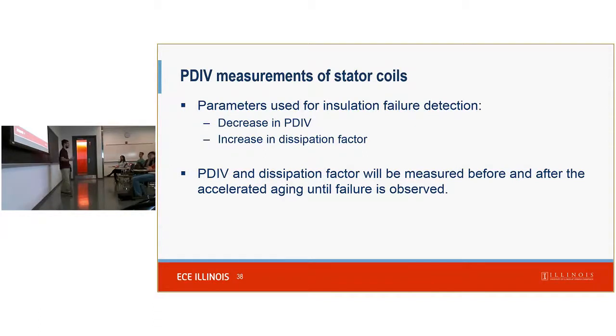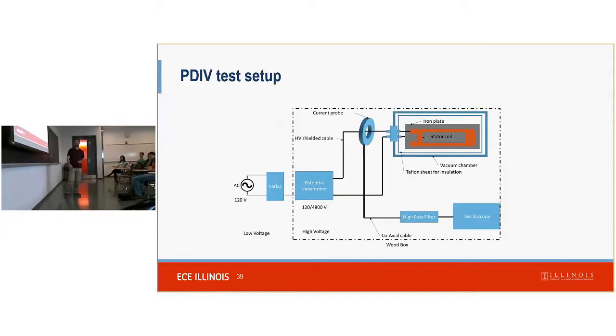And so over time, as you have partial discharge, it will eventually typically cause a dead short, which is not where we want to go. And so the significant part of our testing has been PDIV inception testing, which is where you increase the voltage progressively until you start to observe partial discharge. And we've used that to qualify the various coils.